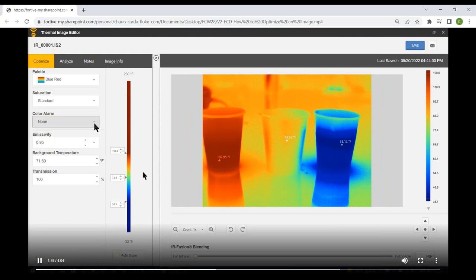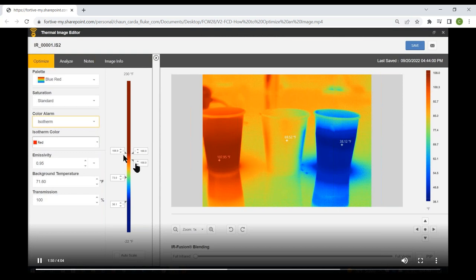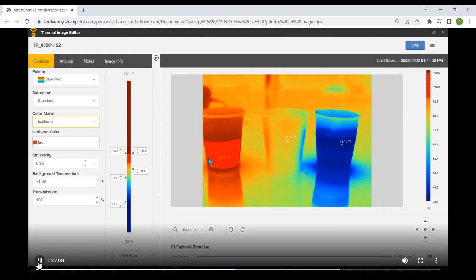Selecting Isotherm causes an additional set of parameters to appear. We define a range within our hot and cold points — in this case between 94 and 108 degrees — and assign it an isotherm color of bright red, so everything between those temperatures shows in that bright red isotherm color. We can also change that color to gray, which makes it stand out more clearly in the chart — that's how the isotherm color works.